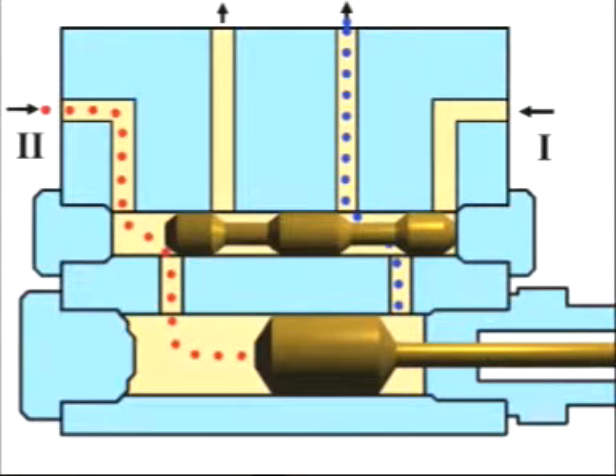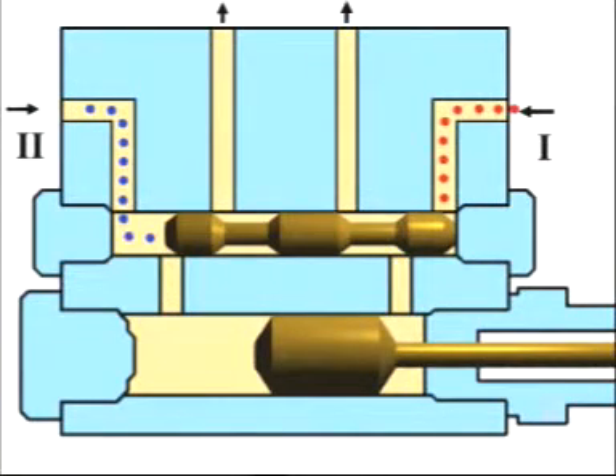Once the delivery piston has reached its final position, the pressure continues to rise in the main line two until the changeover pressure set for the two-line system is reached. The pressure changes over again from main line two to main line one and the process is repeated.